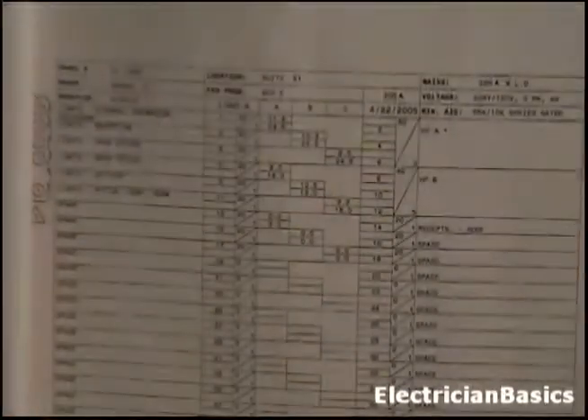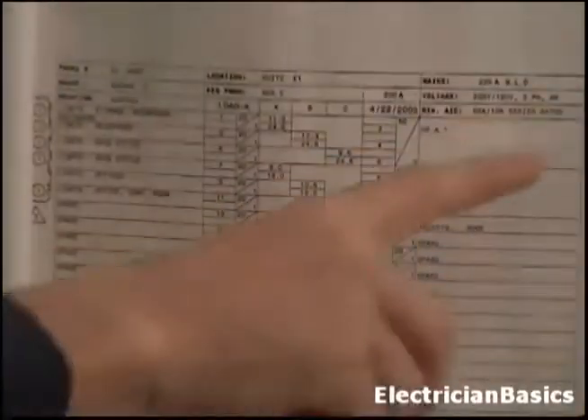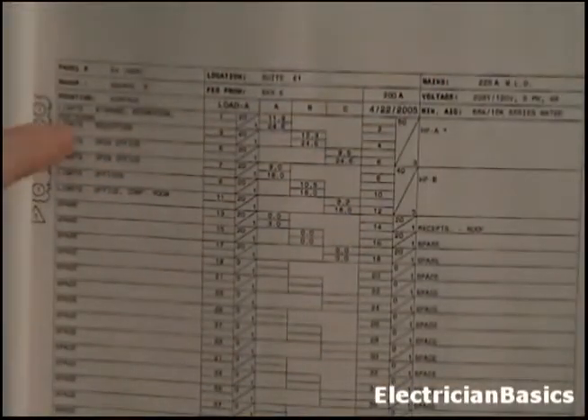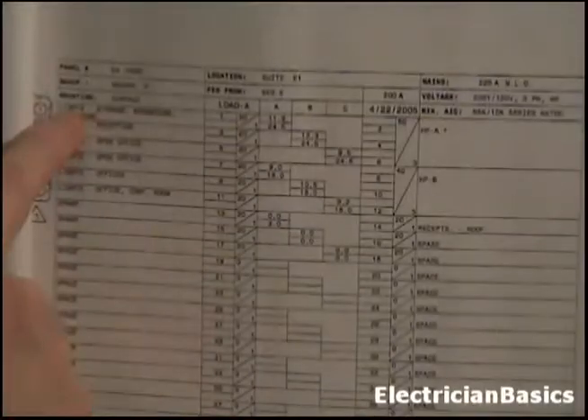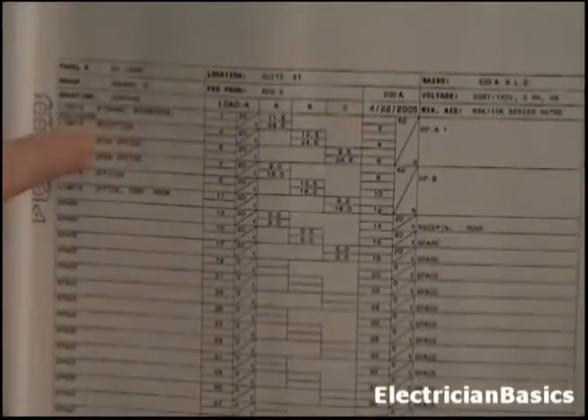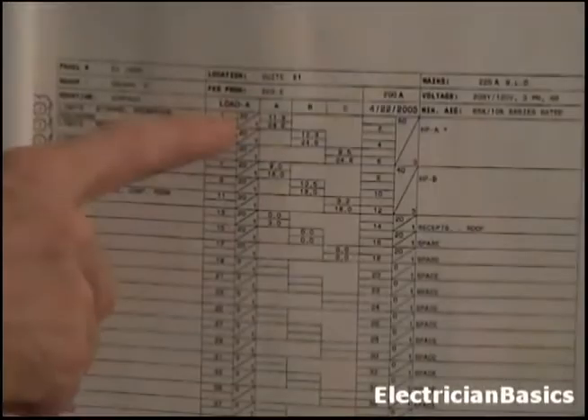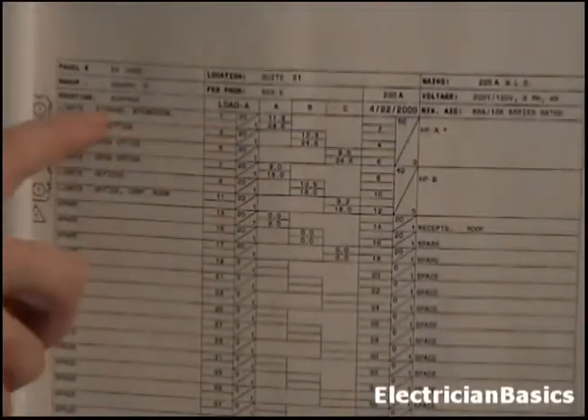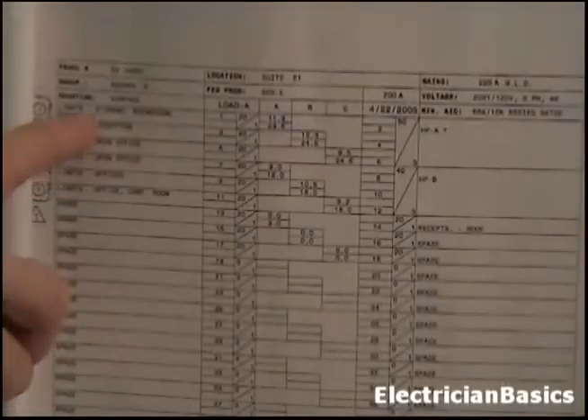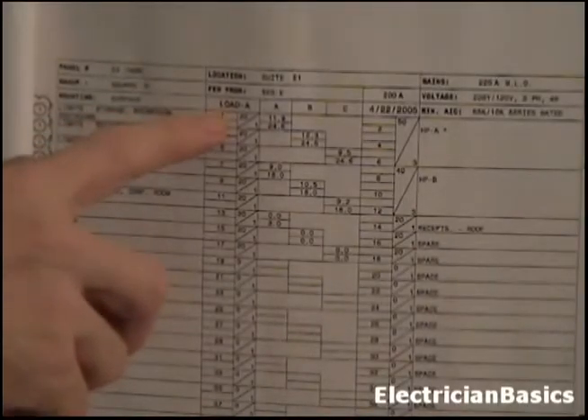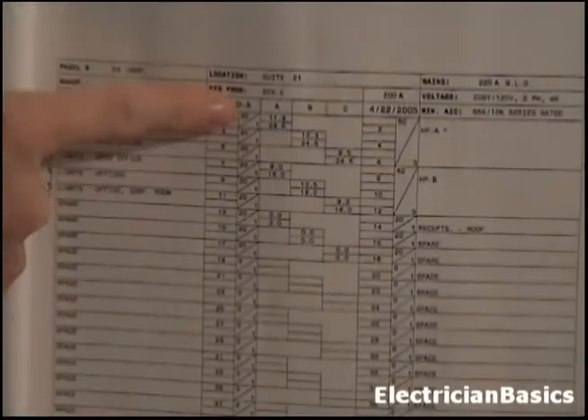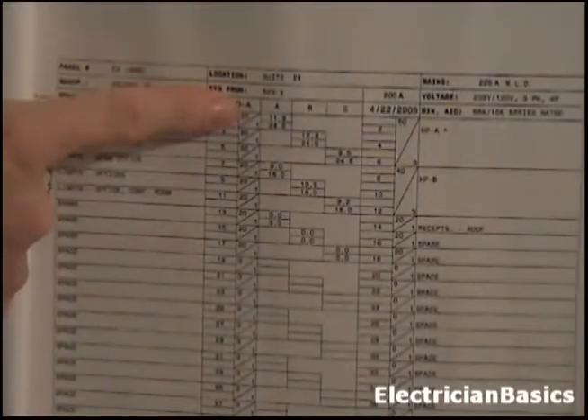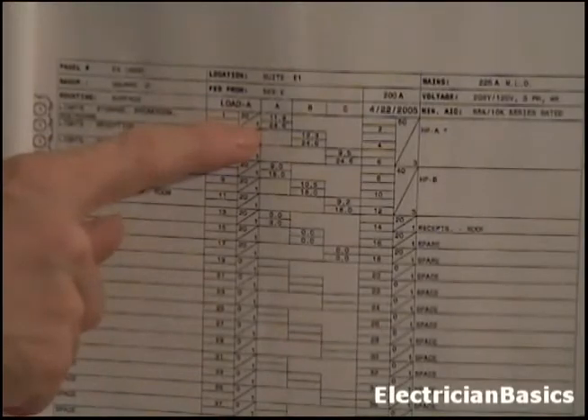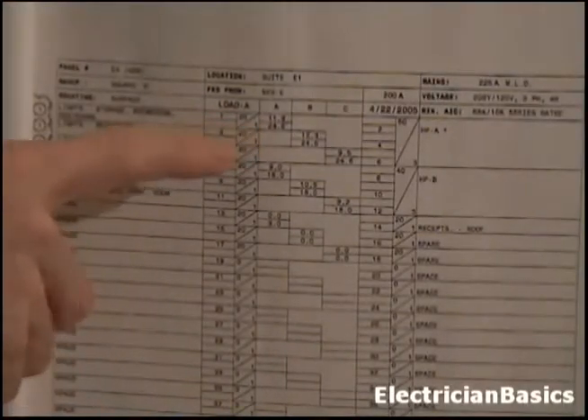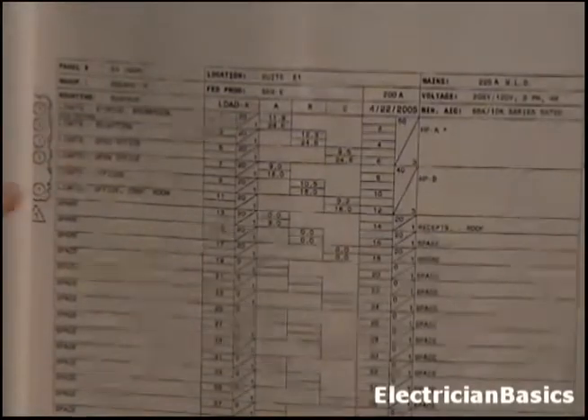Okay, so we've taken kind of an overview look at this information here. First we talked about the lights. If you can read here the lights, okay, in the storage, break room, and restrooms. And that's circuit 1. So this tells what it is and the location. So it's lights in these areas, and it's circuit 1. Now this is 20 amps on this circuit breaker, and it's a single pole breaker, which means that that circuit breaker only controls circuit 1.